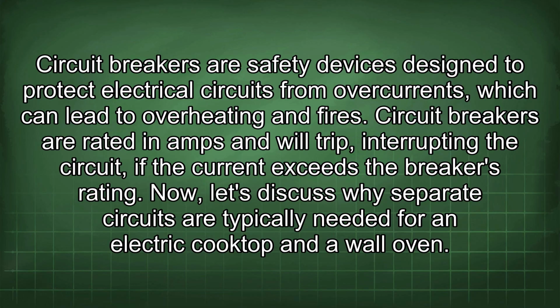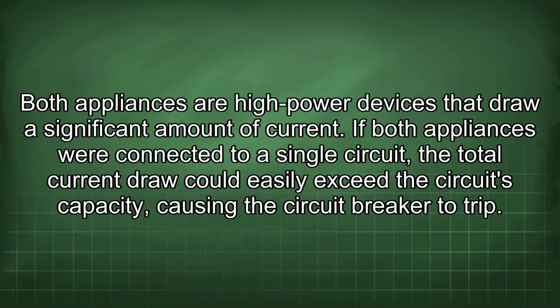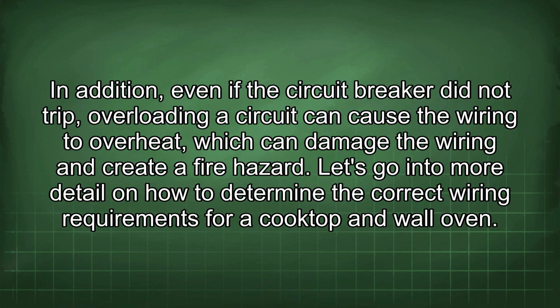Now let's discuss why separate circuits are typically needed for an electric cooktop and a wall oven. Both appliances are high-power devices that draw a significant amount of current. If both appliances were connected to a single circuit, the total current draw could easily exceed the circuit's capacity, causing the circuit breaker to trip. In addition, even if the circuit breaker did not trip, overloading a circuit can cause the wiring to overheat, which can damage the wiring and create a fire hazard.